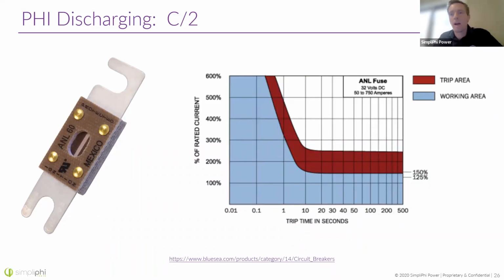Just like you would buy a fast blow fuse to protect your ammeter, you want to do the same kind of thing to protect your electrical equipment. Here's an ANL fuse. It's a 60 amp rating as well. And you can see at 60 amps, this thing will never trip. Keep this in mind if you're using these things to protect your equipment, right? You have to get to almost 140% of load. And even then it's going to take 20 seconds or so in order for this fuse to blow.